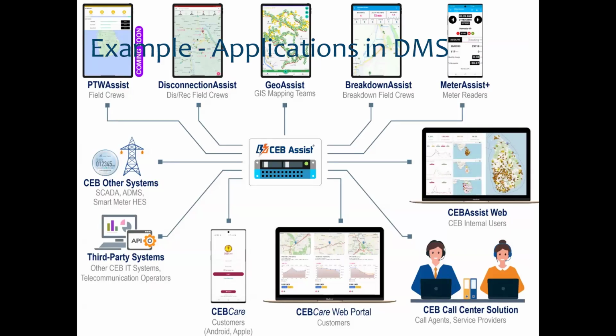This example is from CEB regarding the applications in DMS. An example of an application is the distribution management system. Disconnection Assist is for disconnection of power when payments are not done properly. GeoAssist is for geographic information system mapping for teams, which means all distribution feeders, transformer locations, and 33 kV feeder information are mapped. Breakdown Assist is for breakdown field crews. They can select the number of breakdowns received, where those are located, and what types of faults they are. They can use that application to assist breakdown rectification. And Meter Assist is for meter readers, for entering meter reading values, producing bills, that sort of thing.